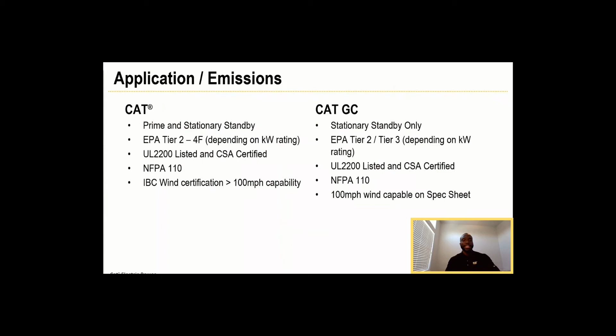Going a little deeper into the Caterpillar offerings: for the CAT traditional product, we have prime and standby. With our CAT GC, we just have stationary standby only. We go anywhere from EPA Tier 2 all the way to Tier 4, depending on the kW rating, for our traditional CAT product, whereas for CAT GC, since it's standby, we only need to be EPA Tier 2 or Tier 3, depending on the rating. All of our products are UL 2200 listed, CSA certified, NFPA 110, and also meet 100-mile-an-hour wind capabilities.